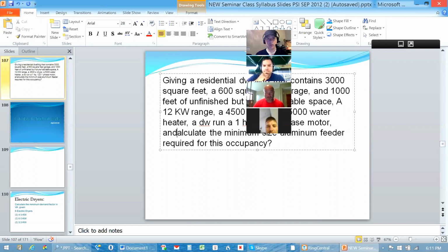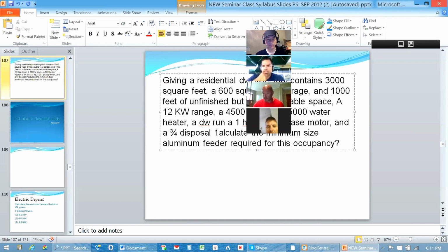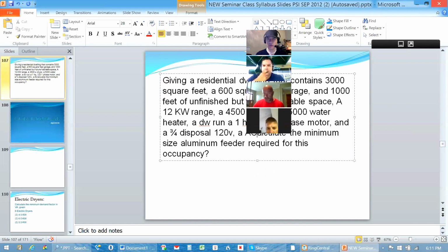And a disposal that's a 3/4 horsepower at 120. An air conditioner. It seems like lately they've been giving AC units as an actual amperage value, and then the voltage rating as well. So they give you an AC heat pump unit that's like 30 amps at 230 volts. Okay, so 30 amps at 230 volts.